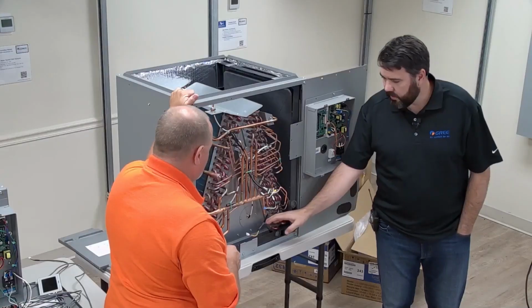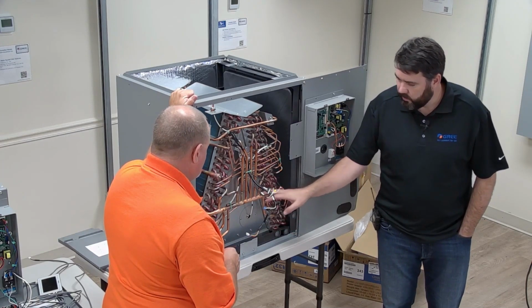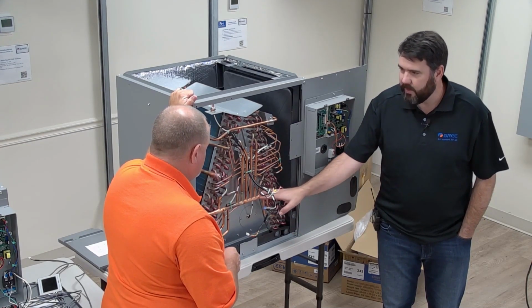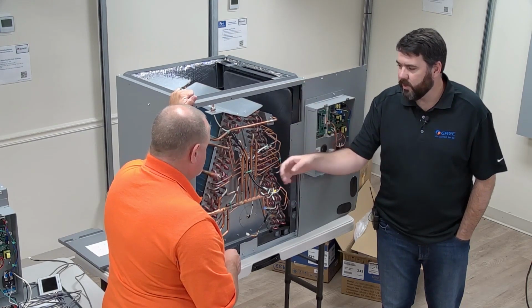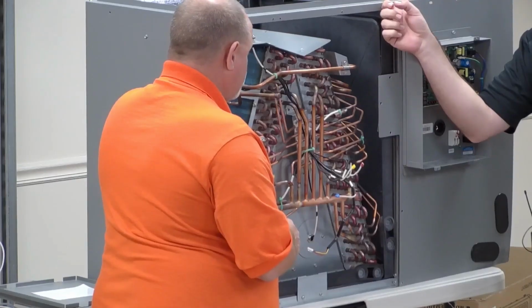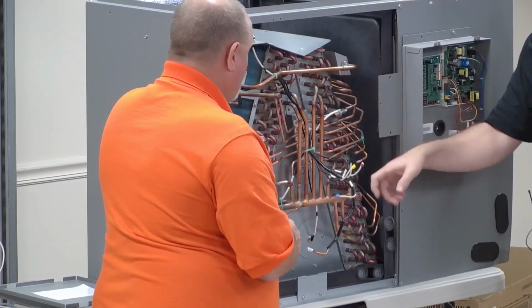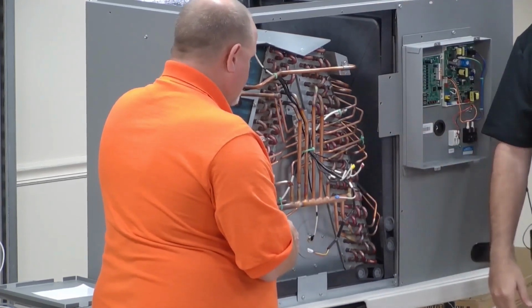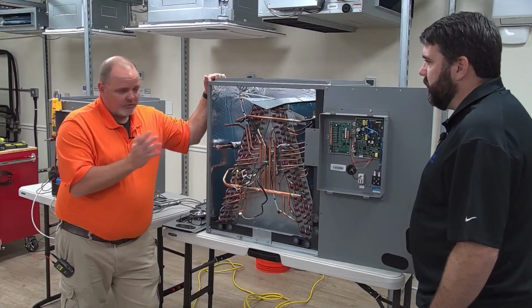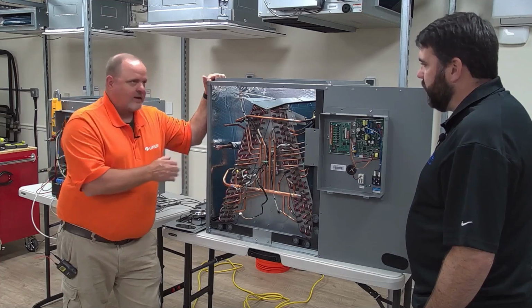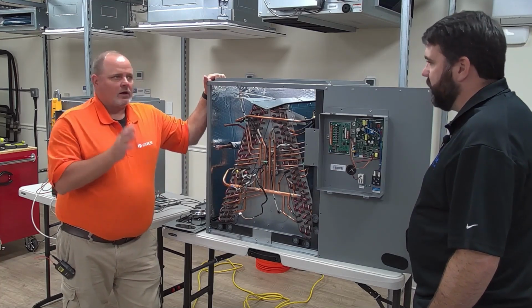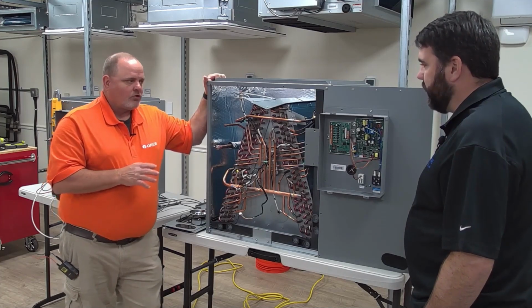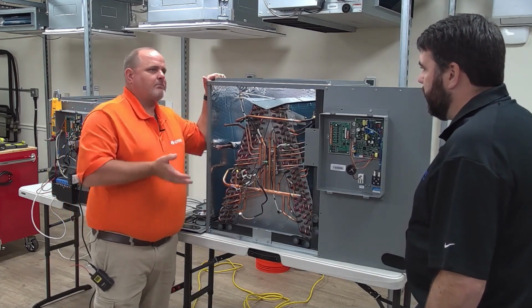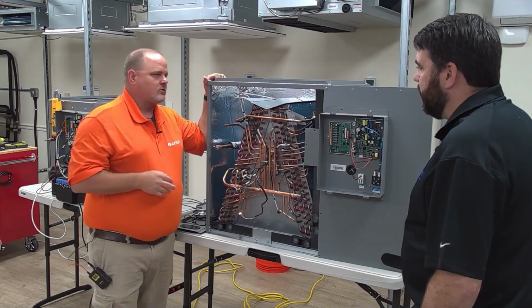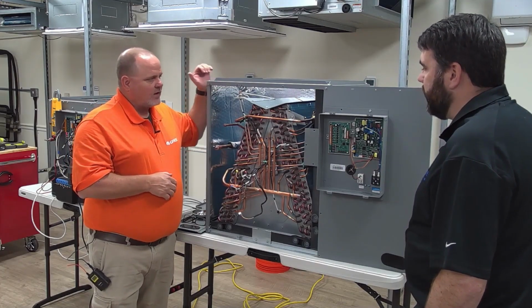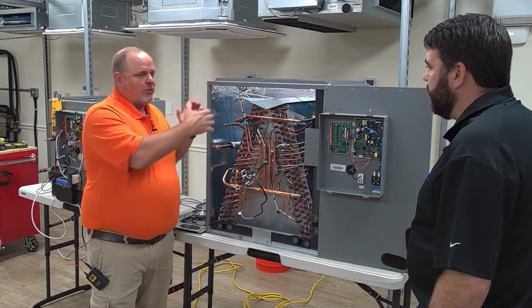The other thing that you taught me was to go ahead and put the coil back in here before. Don't just leave the coil out and then install this case, because then you may torque it and then this thing won't slide in there smoothly. Yes. So what Daniel was saying there was, if you're converting it, you convert it, you put the coil back in, you take the coil all up there, and then you get it all hooked up to your ductwork. Don't leave the coil out. Take the box up, get it all installed, and then try to slide the coil in. Because if you do that, chances are without the coil in there, you may rack the case.